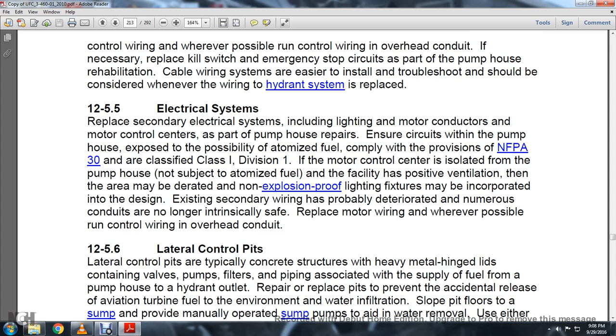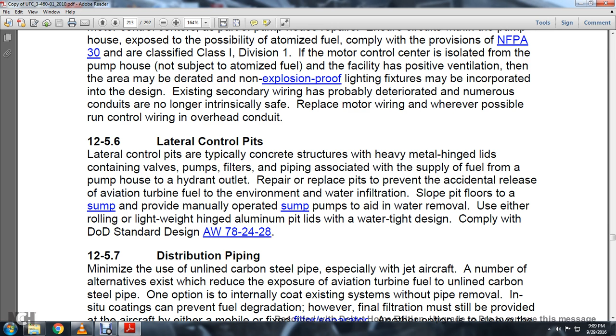12.5.6 Lateral control pits. Lateral control pits are typically concrete structures with heavy metal hinged lids containing valves, pumps, filters, and piping associated with the supply of fuel from the pump house to the hydrant outlet. Repair or replace pits to prevent the accidental release of aviation turbine fuel to the environment and water infiltration. Sump pit floors should slope to the sump, which provides a manually operated sump pump stage for water removal. Use either rolling or lightweight hinged aluminum pit lids with a watertight design comply with the Department of Defense standard design AW 78-24-28.